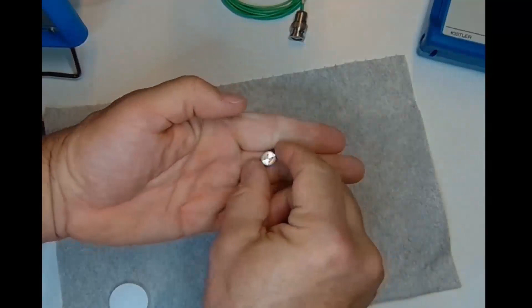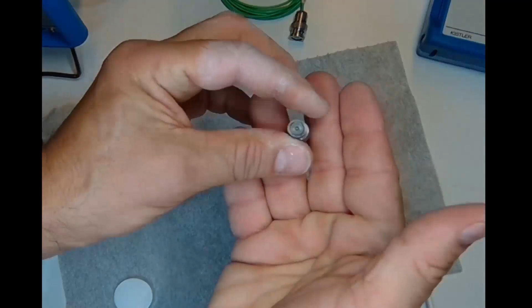Another example is this sensor. It's just after the test with the cap, and as soon as you finish the test, you remove the cable and immediately mount the cap. Now we have to clean the sensor. First, clean like this, check whether there is a sealing ring or not, and then remove the cap. Very easy. So this is the cap, and this is the sensor. Again, clean the membrane properly. You see the second sealing ring. Clean it. Use a piece of textile, and that's it. Wait a little bit. Yeah, you can see here.